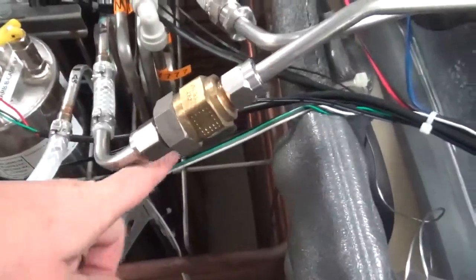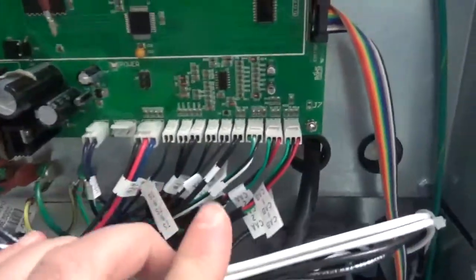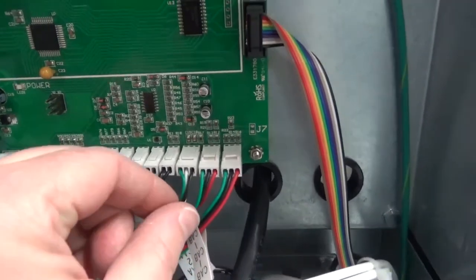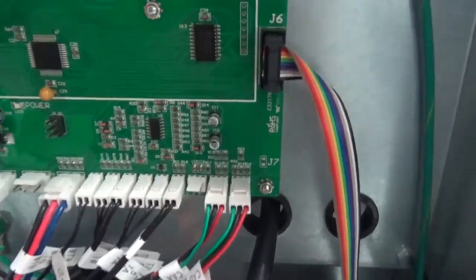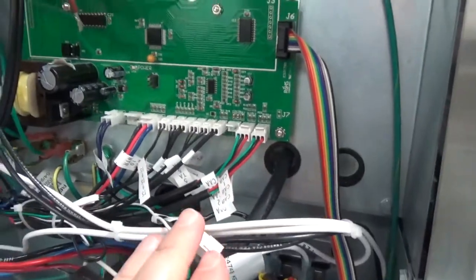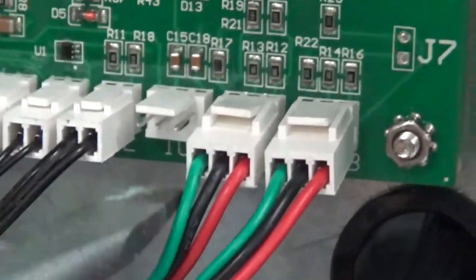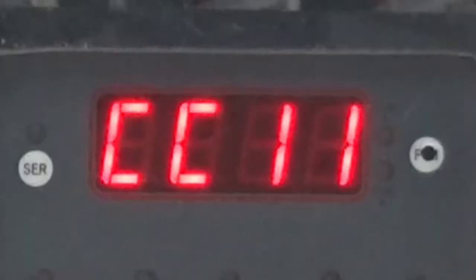If we still don't see CC11 on the display, remove the wire harness from the control board and jump all three pins on the control board. CC11 should appear. That tells us that the board is good and the ice bank control probe is bad.